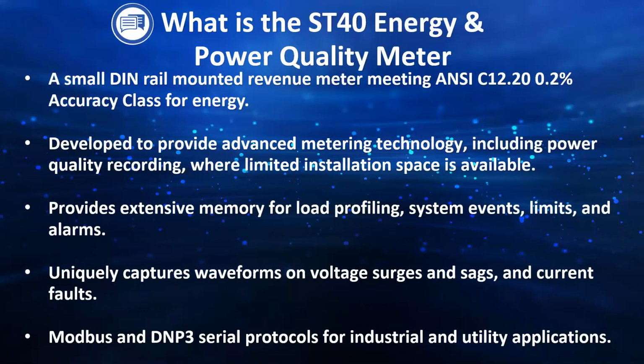You can capture system events. You can set limits. So for your voltage, for your current, for even your power factor, which is a very good way to measure the efficiency of your equipment, you can set limits so that if my power factor goes below 0.8, that means my efficiency is going below 80%, I want to know. So the meter, through the software, will tell you that your voltage is unbalanced, it's going up and down, or your power factor is going down. You can set those types of limits and then get alarms based on those limits. So you can proactively go and make sure that your machinery and equipment is not being affected by bad power being fed into it.